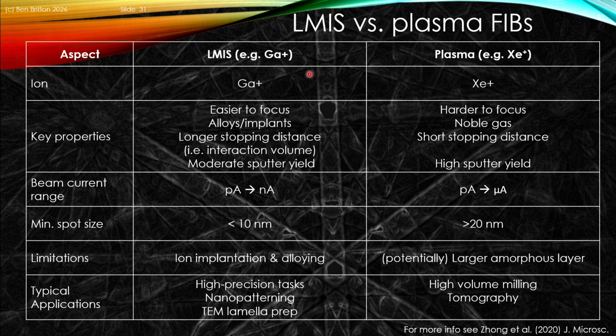There are a whole range of different reasons. We can have this very simple sort of table. This is the liquid metal ion source. This is the plasma source. There are of course different ions we can choose, as we'll see a bit later. Gallium and xenon are the two we're describing in here. But we have basically that the gallium source, for lots of reasons, is relatively easy to focus. It alloys and can implant. It has a relatively long stopping distance, and that means it controls something about the interaction volume. And it's reasonably heavy, but it has a moderate sputter yield, and so that can reduce the effective cutting rates of this system.